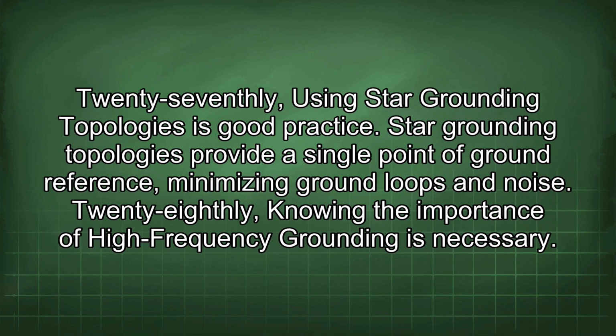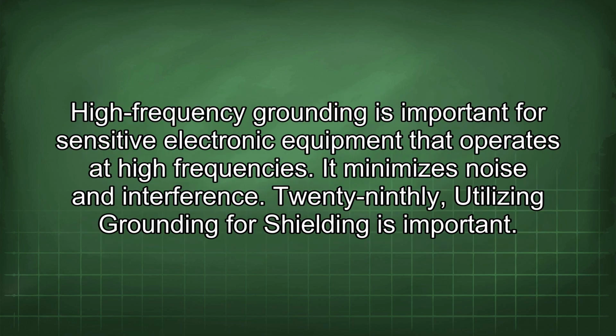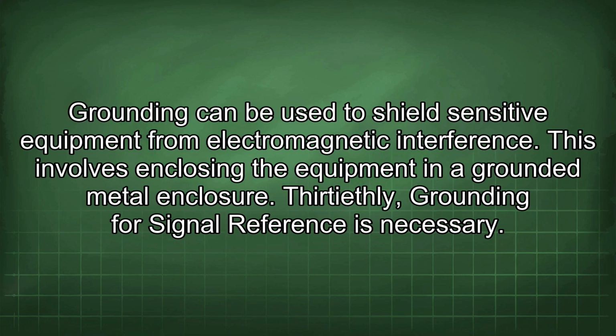Twenty-seventhly, using star grounding topologies is good practice. Star grounding topologies provide a single point of ground reference, minimizing ground loops and noise. Twenty-eighthly, knowing the importance of high-frequency grounding is necessary. High-frequency grounding is important for sensitive electronic equipment that operates at high frequencies. It minimizes noise and interference. Twenty-ninthly, utilizing grounding for shielding is important. Grounding can be used to shield sensitive equipment from electromagnetic interference. This involves enclosing the equipment in a grounded metal enclosure.